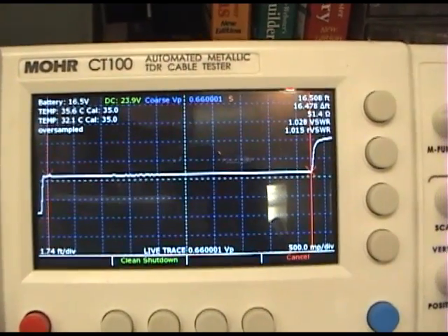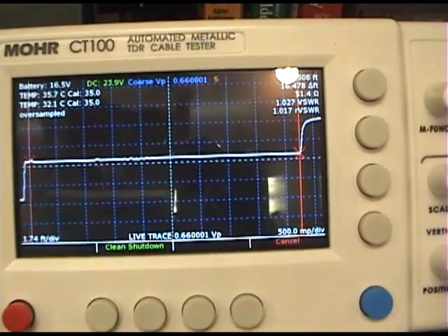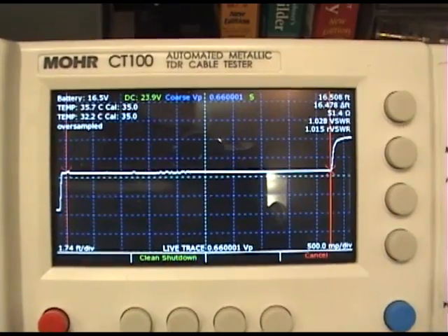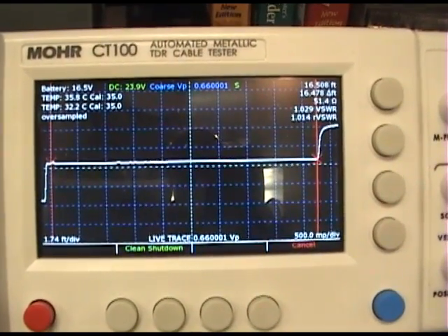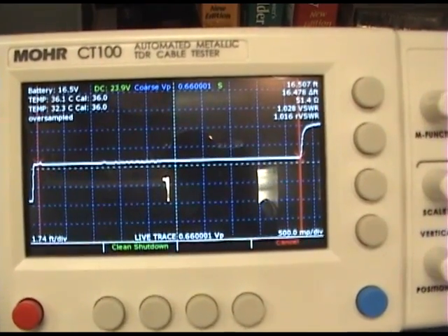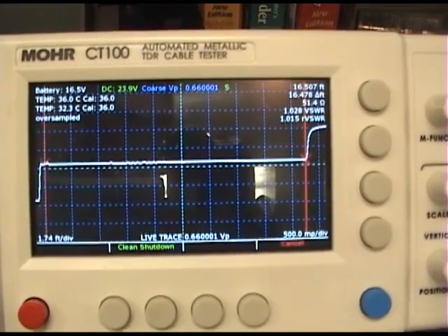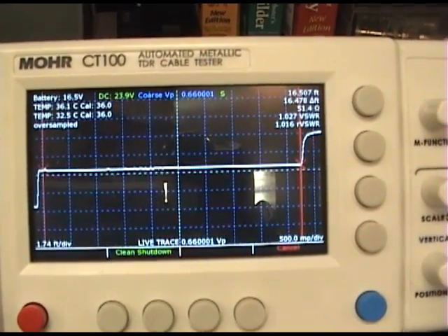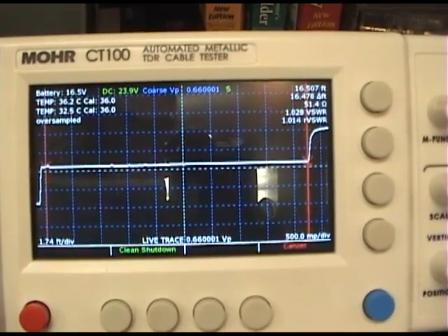The TDR is definitely more accurate than the scope. But, the calculation is pretty accurate, within a few inches. You probably don't want to use a scope as a TDR for extremely large runs as your error will increase.